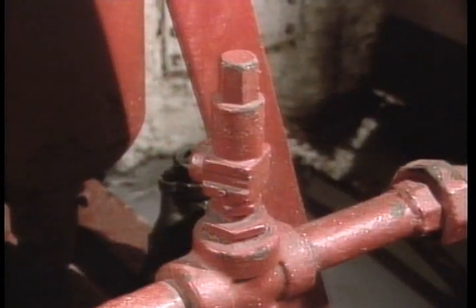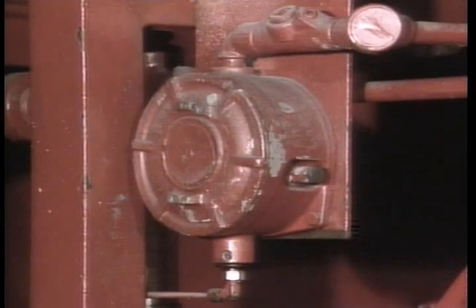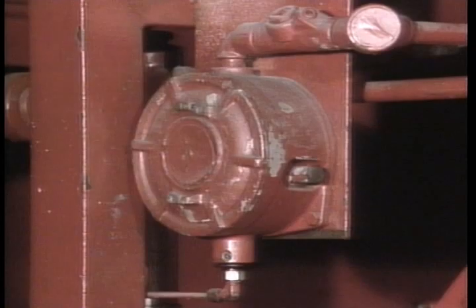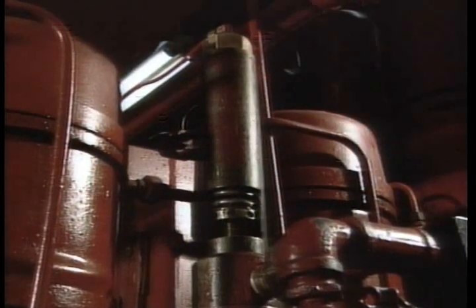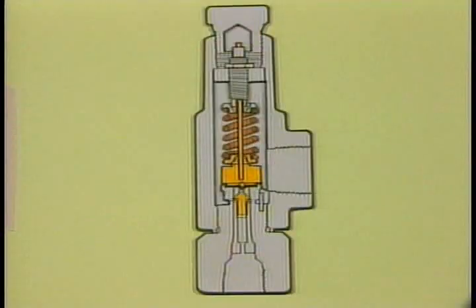These are the system's maximum pressure relief, or pop-off, valves. In the event the hydraulic automatic pressure switch or hydro-air pressure switch fails and system pressure increases, the relief valves will open and allow fluid to flow to tank until the problem can be corrected.